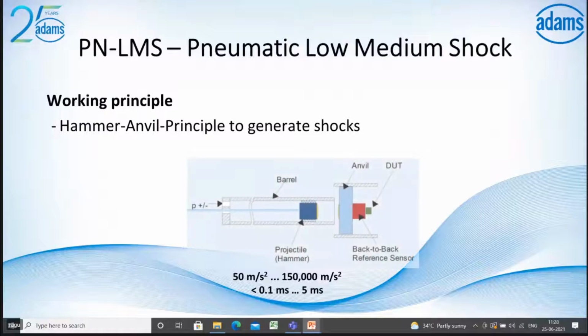Now, how does it work? It's based on the hammer anvil method to generate the shocks. It's a pneumatic driven pulse generator, a pneumatic driven shock exciter, which provides a wide amplitude range. Within a barrel, a projectile is accelerated by pressurized air used as the hammer, and the air pressure is kept constant. The kinetic energy of the projectile can be controlled by the motor driven mechanical stop, which allows a precise adjustment of the projectile starting position, that is, the distance over which it gets accelerated.